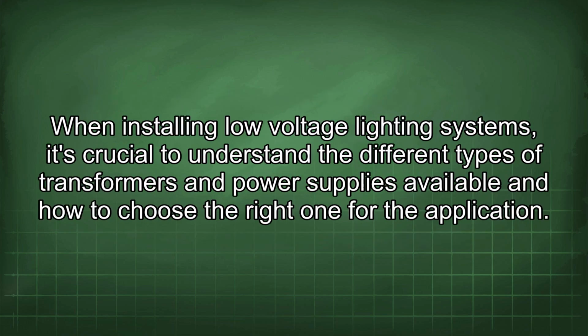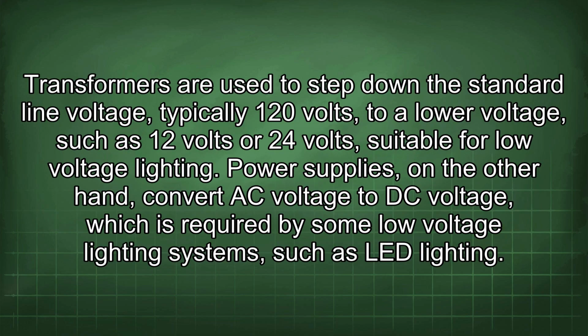When installing low-voltage lighting systems, it's crucial to understand the different types of transformers and power supplies available and how to choose the right one for the application. Transformers are used to step down the standard line voltage, typically 120 volts, to a lower voltage such as 12 volts or 24 volts, suitable for low voltage lighting. Power supplies, on the other hand, convert AC voltage to DC voltage, which is required by some low voltage lighting systems, such as LED lighting.